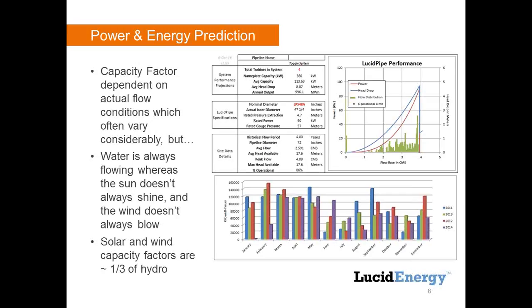Government numbers show solar and wind capacity factors are about a third of hydro. So even though we started with 360 kilowatts and went down to 113, it's still three times more than a solar application. If you wanted an effective 100 kilowatt capacity, you'd have to size a solar or wind farm at 300 kilowatts to match what a 100 kilowatt hydro system delivers. So hydro is much more efficient at making energy because it's usually always flowing — solar and wind have to be sized three times bigger to get the same effective capacity.